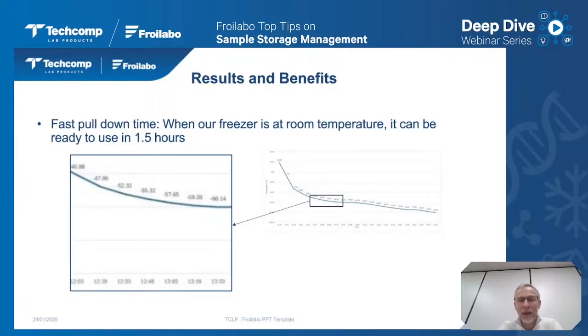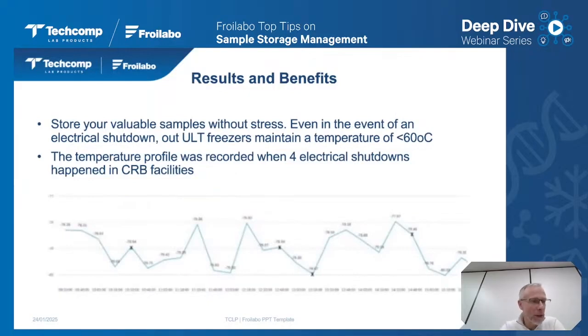And -60 degrees means that they can transfer the samples into the units, because it's sufficient to be safe for the samples. Also, it's very important in this case to have performant equipment, to be sure that we will be able to manage the transfer of the samples in stress conditions. The second thing is regarding the performance of keeping the temperature at -80 degrees, even when something happens. After turning on the unit in the facilities, they faced several electrical shutdowns in the building.